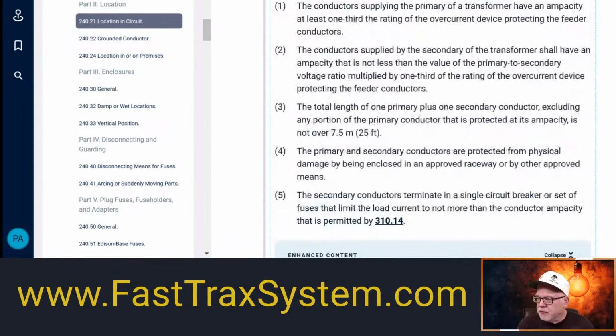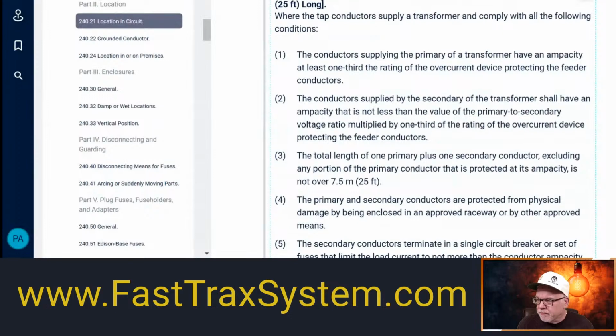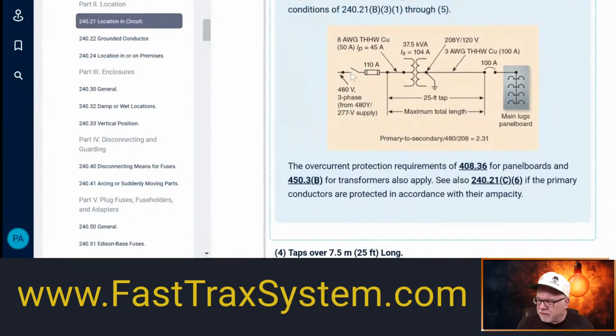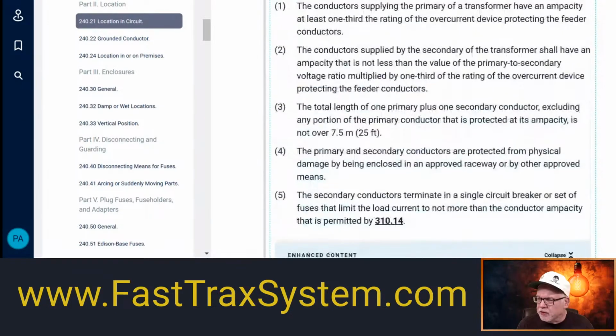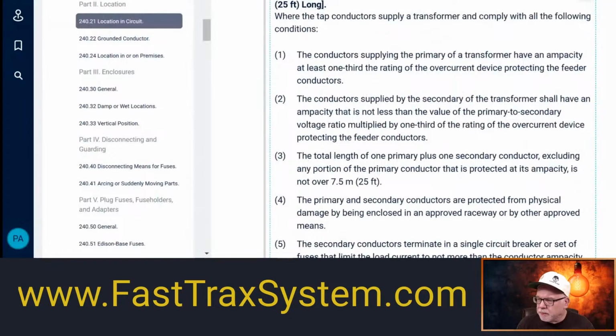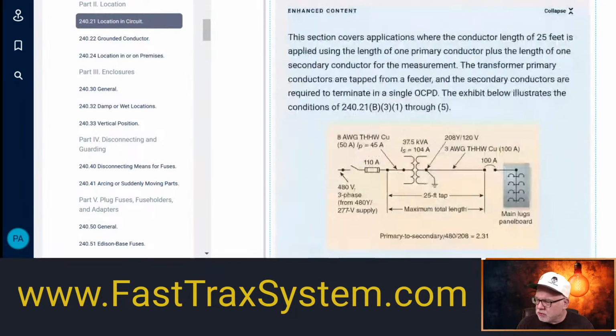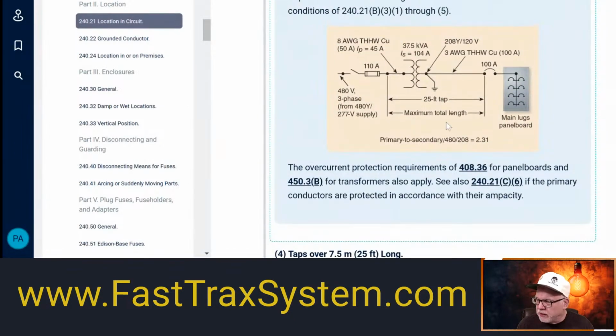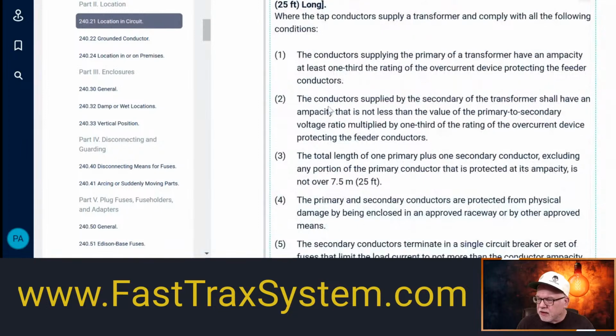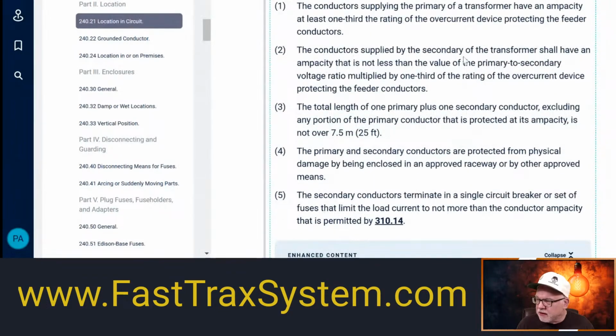So let's do the math. So a normal transformer, we'd be okay feeding it, everything good. But let's see if we're good in this scenario. All right, primary to secondary voltage ratio. That is 2.31. We got it. It says the conductor supplying the secondary of the transformer shall have an ampacity not less than the value of the primary to secondary ratio multiplied by 1/3 of the rating of the overcurrent protection of the feeder.